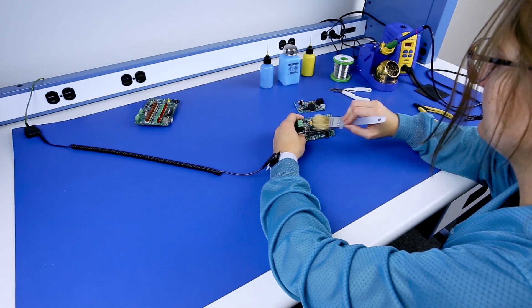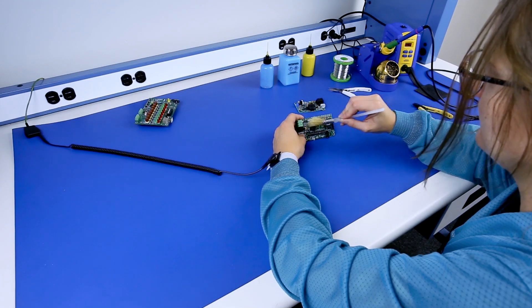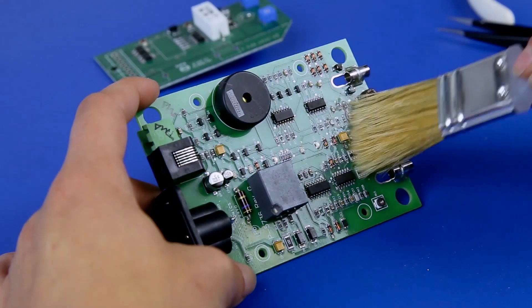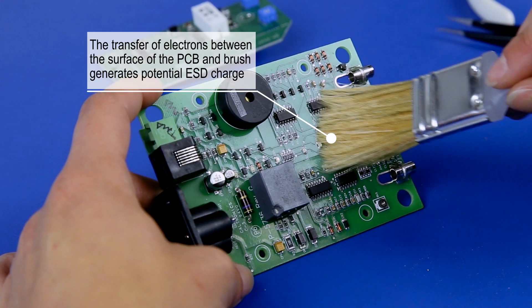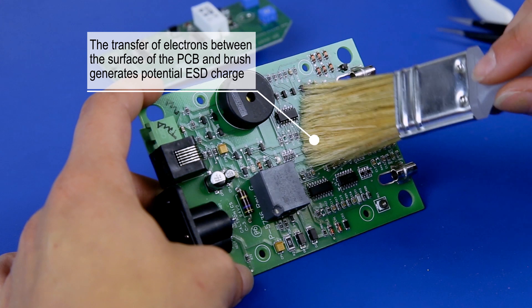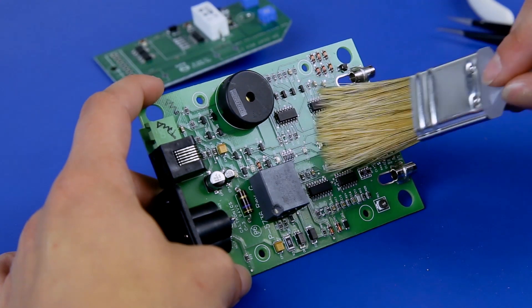When a regular brush is being held by a worker and wiping upon a product or assembly, tribocharging occurs due to the contact and separation of the brush fibers on the product. Per the ESD handbook, ANSI/ESD TR20.20 section 2.4, sources of static electricity include brushes.